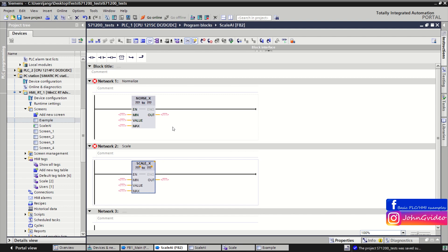The NORM_X function — normalize — can be used to normalize the value of the tag at the value input by mapping it to a linear scale. You can use the minimum and maximum parameters to define the limits of the value range. The result is output to the OUT output, where it is calculated and stored as a floating point number. For example, if the value to be normalized equals the minimum input, the output has the value 0.0, and if it equals the maximum input, the output returns the value 1.0.